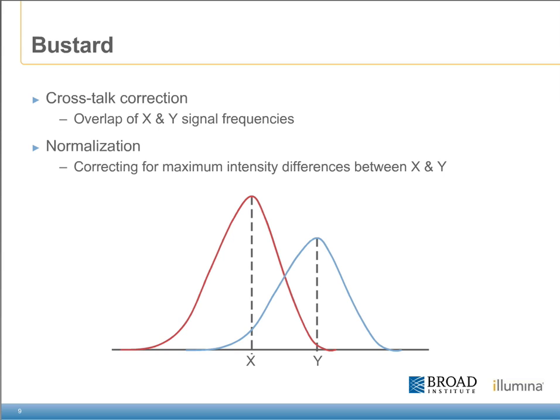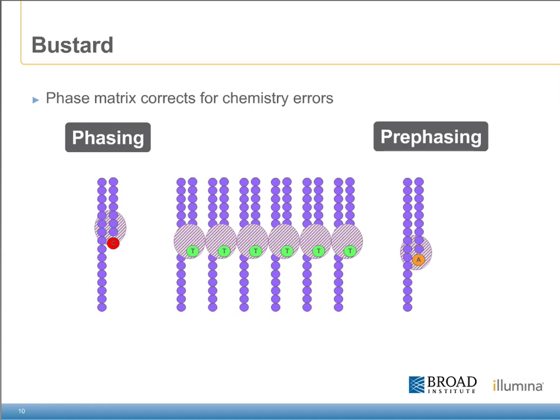Besides crosstalk, there is also normalization for the maximum intensity differences between each of the dyes. Bustard also tries to make a correction based on the phasing or pre-phasing that happens within the chemistry. Due to minor inefficiencies in the chemistry, it's possible for a small number of molecules that make up a cluster to be either a base ahead or a base behind the current incorporation cycle. These molecules that are out of phase with the majority can account for an additional signal. The software uses a number of algorithms to correct for this phasing or pre-phasing signal.